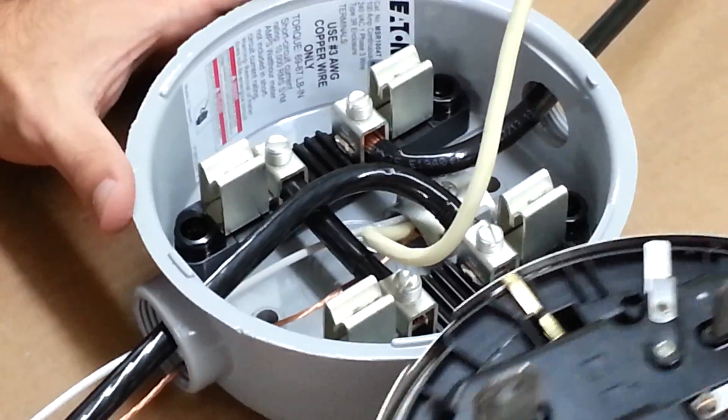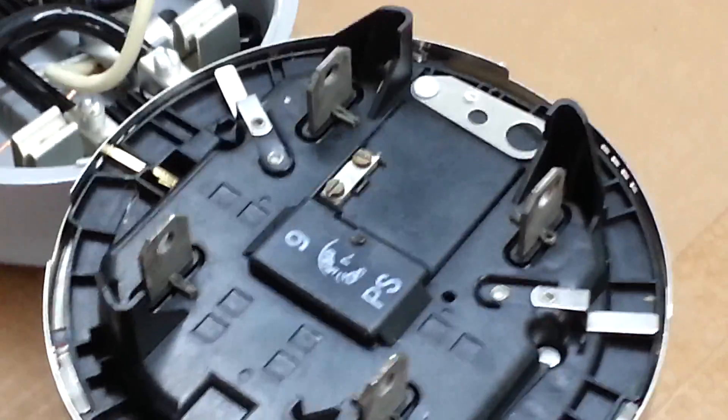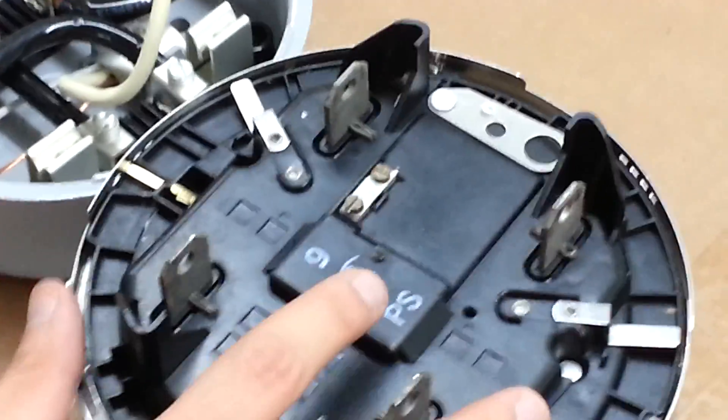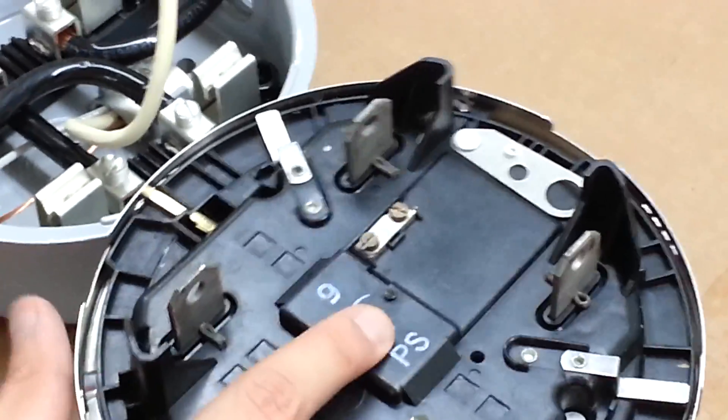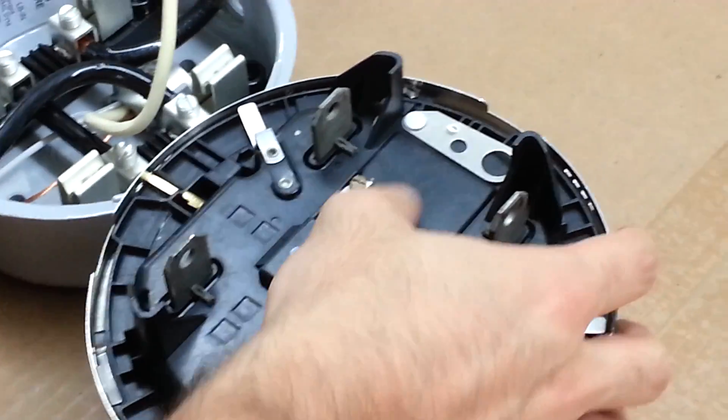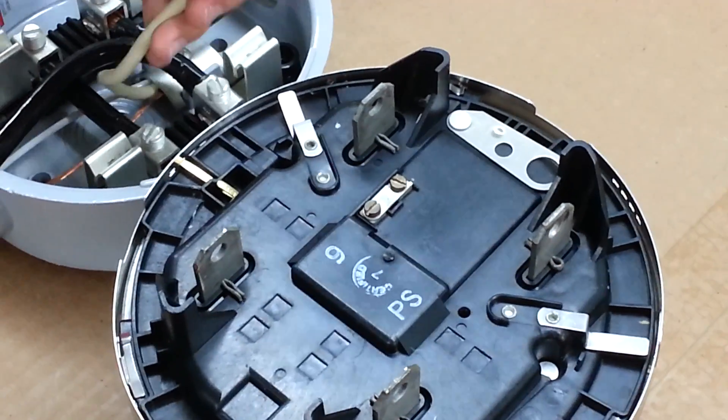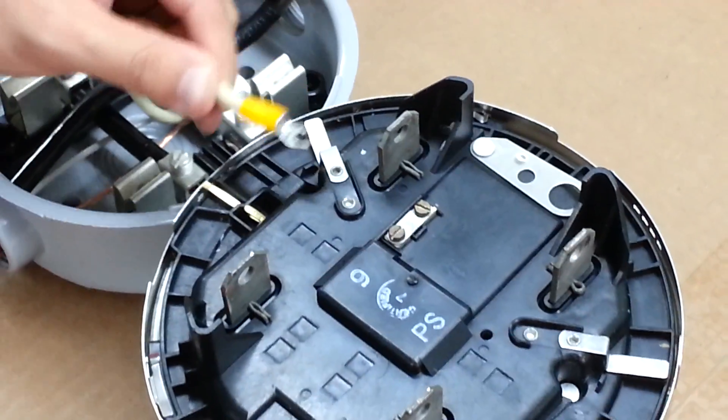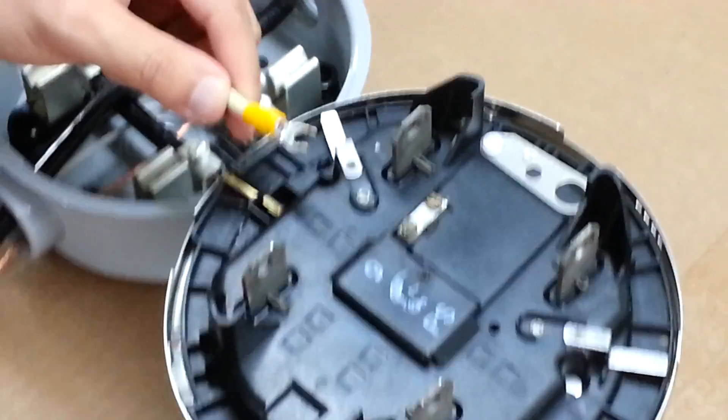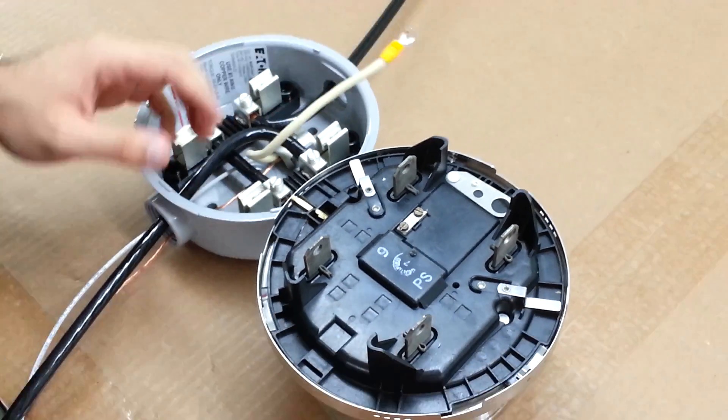Now this step is very important that a lot of our customers miss. On the back of the meter, you are going to see a potential clip with two screws. This jumper wire needs to be connected to the screw that swivels on the clip.